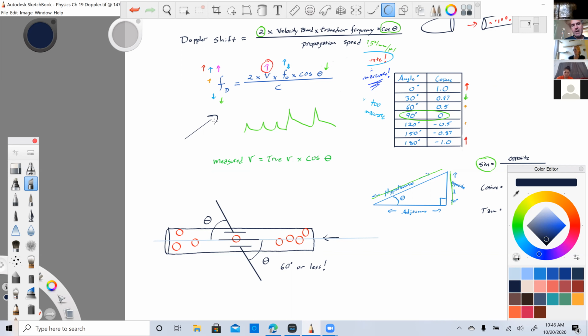The angle correct is basically telling us the difference between, well, this. If you don't have an angle correct at all, the computer has to assume a 0, and we'll put 1 in the equation. 1 being the largest number. Is that going to be an overestimate? It would seem like it would underestimate. Well, in any case, you now have an incorrect velocity.